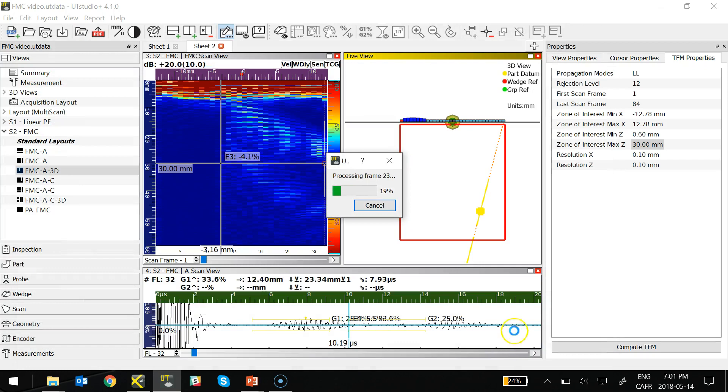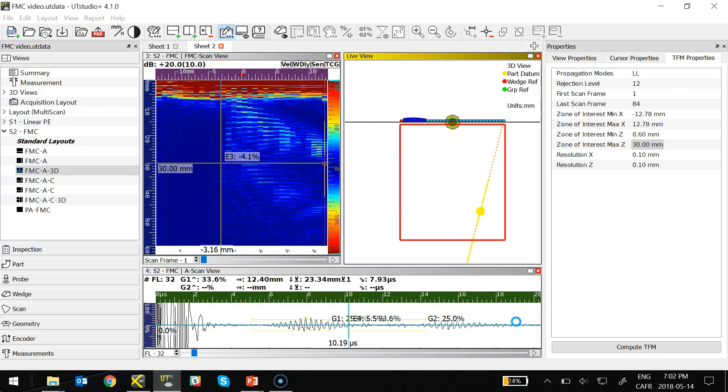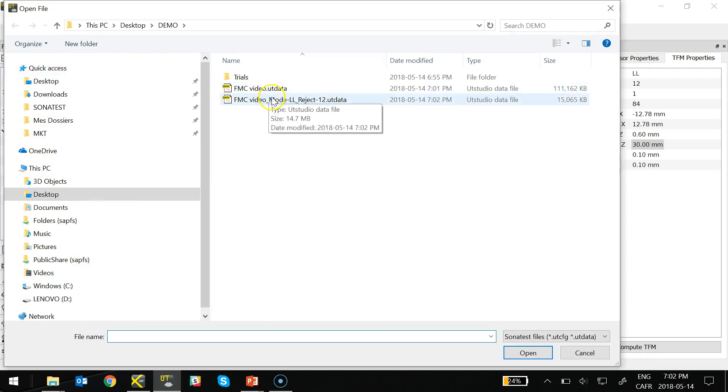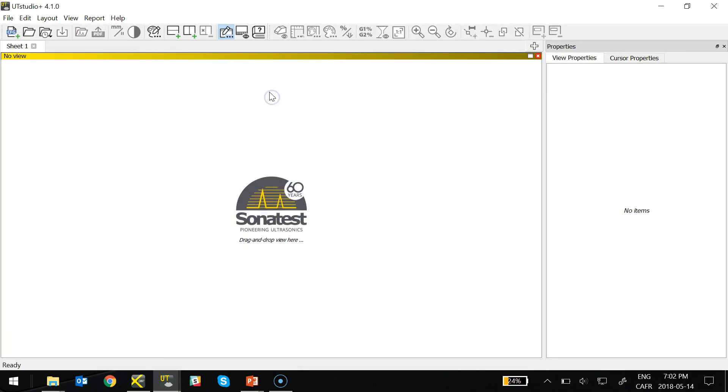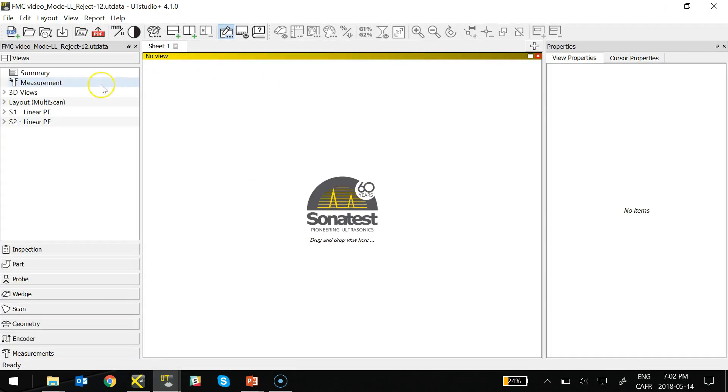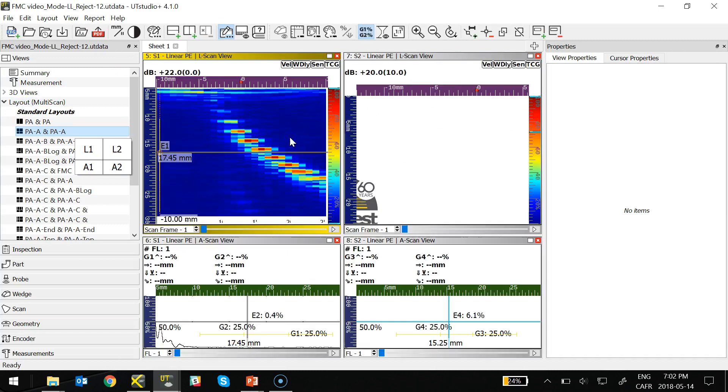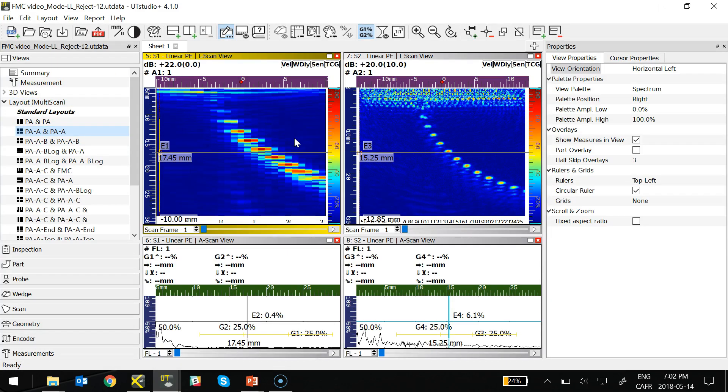Now, computing my TFM images, I use the LL mode, and I'm computing directly under the probe. By doing that, I'm creating a new set of data files, a new UT data, having the TFM images in it.